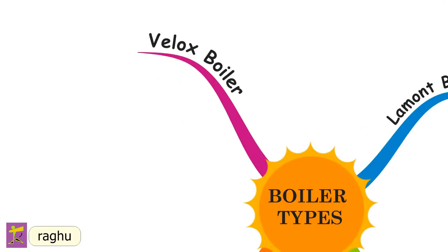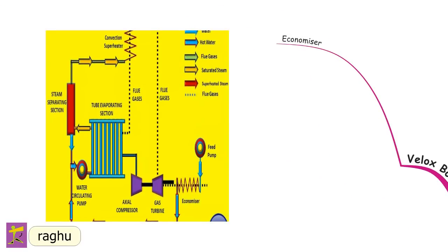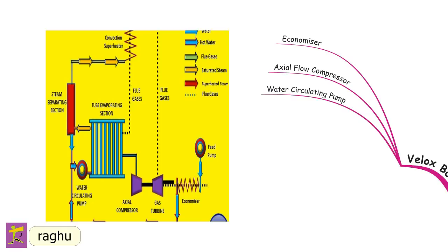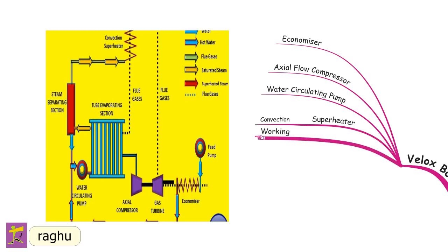The Velox boiler is a forced circulation water tube boiler mostly used with gas turbines. In this boiler, the velocity of flue gases is greater than the velocity of sound, which causes more heat transfer from gas to water and increases the steam generation rate, making it a very important boiler. The economizer preheats water from the feed pump. An axial flow compressor raises air pressure from atmospheric to furnace pressure. A water circulating pump moves water from the economizer to the tube evaporating section. A convection superheater superheats the steam.